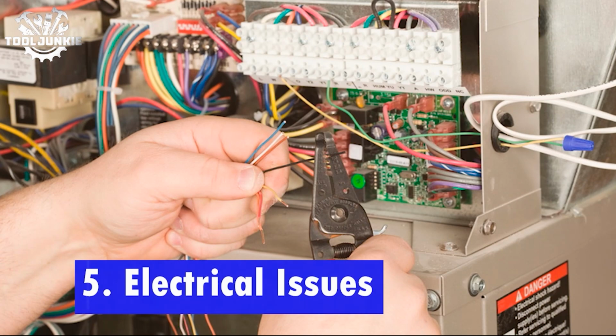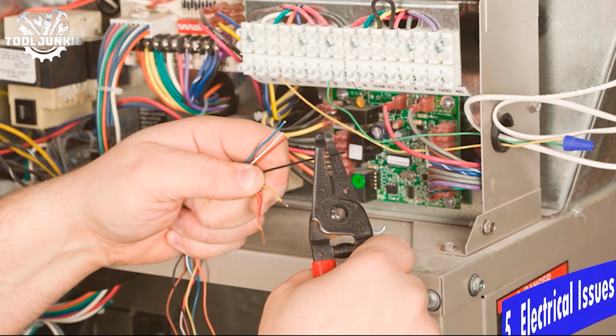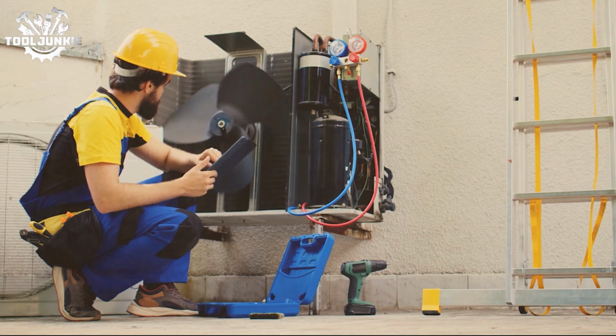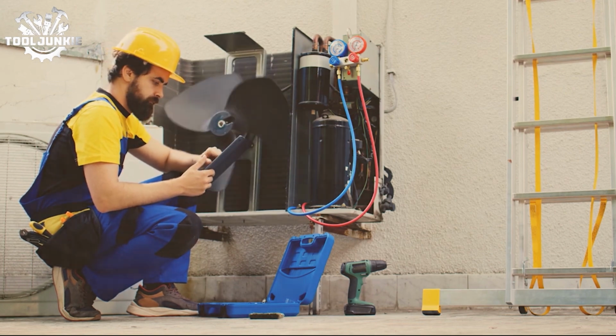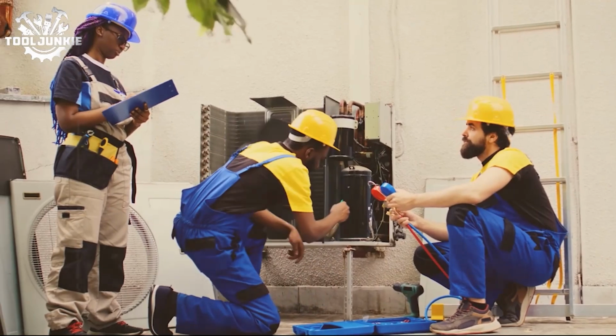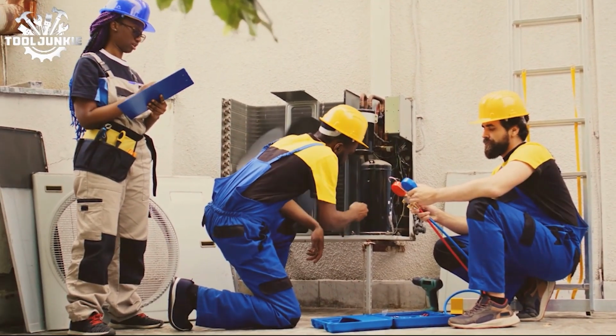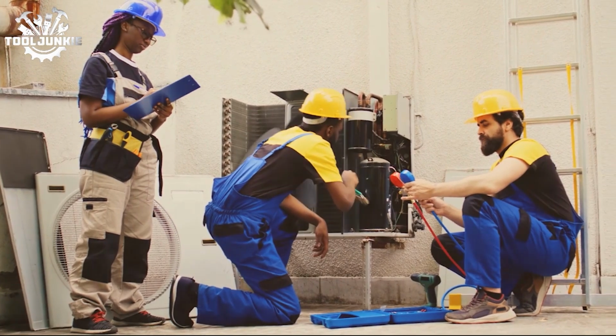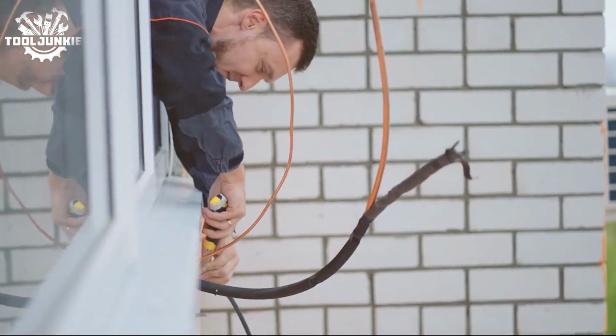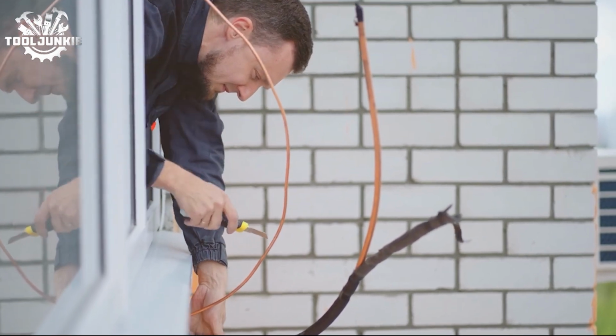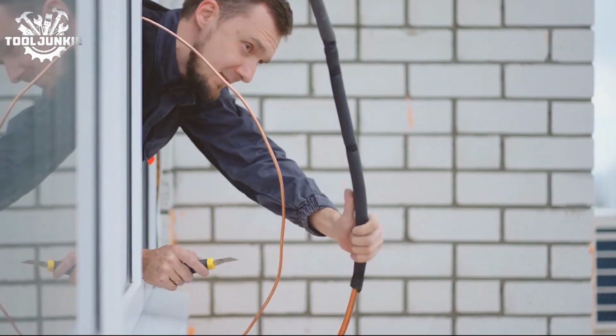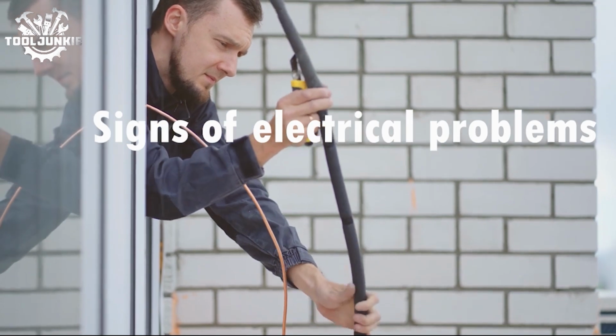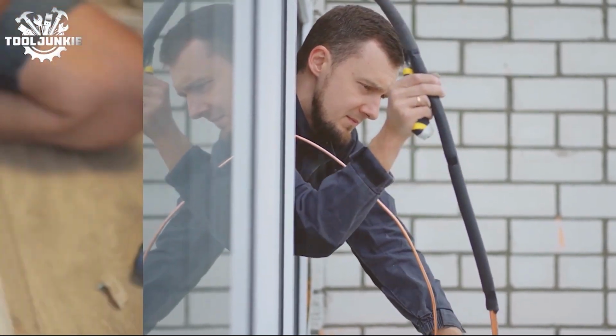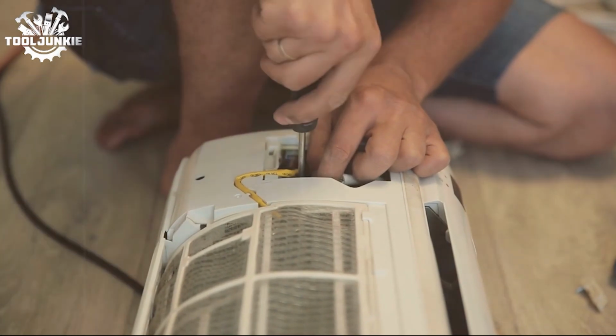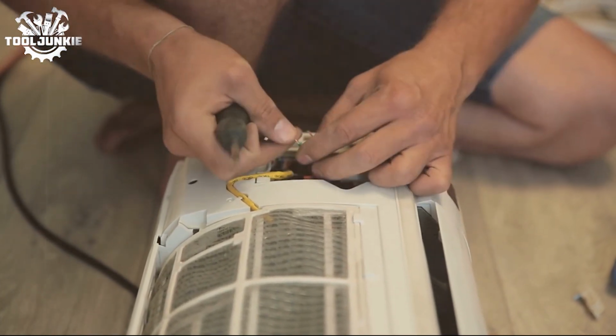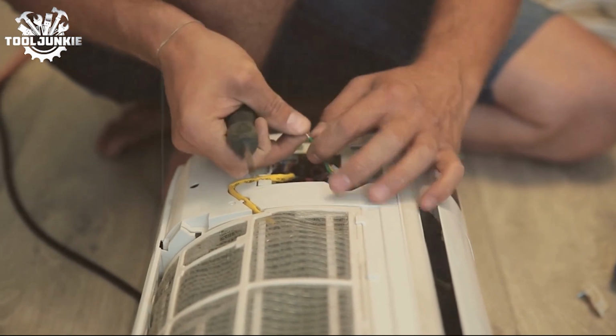Number 5. Electrical issues. Electrical issues can be the hidden gremlins in your air conditioning system. Loose connections, a faulty capacitor, or a malfunctioning control board can disrupt the electrical flow, causing your unit to short cycle. These are not always easy to spot, but signs like a tripping circuit breaker or a stuttering start can be telltale indicators. So, how to identify signs of electrical problems? While some basic troubleshooting can be done by homeowners, most electrical repairs should be left to the professionals for safety and accuracy.